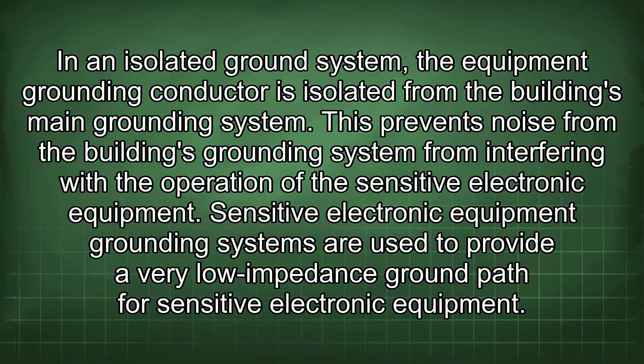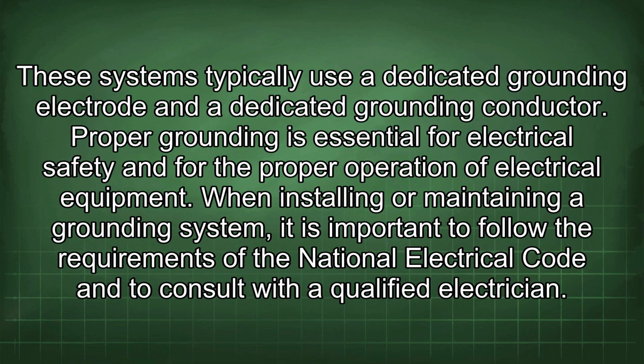Sensitive electronic equipment grounding systems are used to provide a very low impedance ground path for sensitive electronic equipment. These systems typically use a dedicated grounding electrode and a dedicated grounding conductor. Proper grounding is essential for electrical safety and for the proper operation of electrical equipment. When installing or maintaining a grounding system, it is important to follow the requirements of the National Electrical Code and to consult with a qualified electrician.